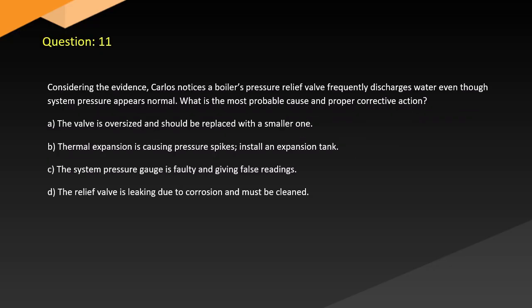Question 11. Considering the evidence, Carlos notices a boiler's pressure relief valve frequently discharges water even though system pressure appears normal. What is the most probable cause and proper corrective action? A. The valve is oversized and should be replaced with a smaller one. B. Thermal expansion is causing pressure spikes. Install an expansion tank. C. The system pressure gauge is faulty and giving false readings. D. The relief valve is leaking due to corrosion and must be cleaned.